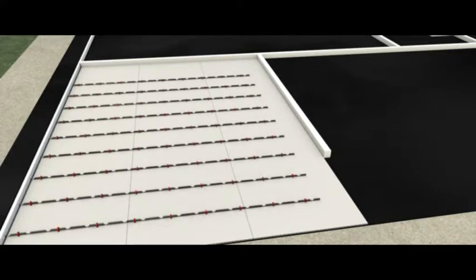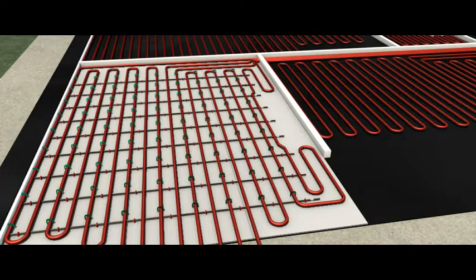Lengths of rapid rail are then positioned roughly a meter apart, running in a perpendicular direction to the underfloor pipe using the red clips provided. The red Qualpex barrier pipe is then positioned according to the pipe layout diagram, using the rapid rail and green clips to hold it in position.